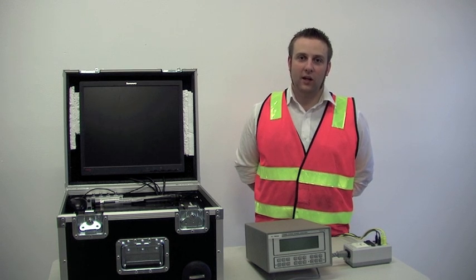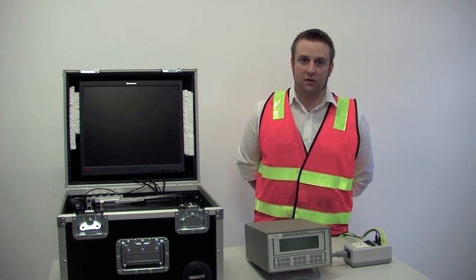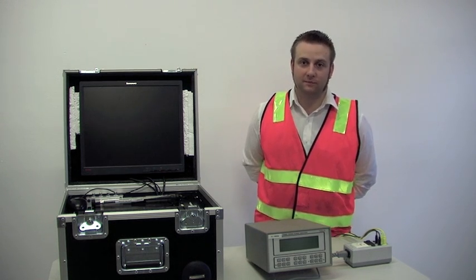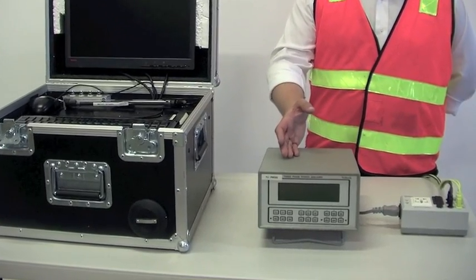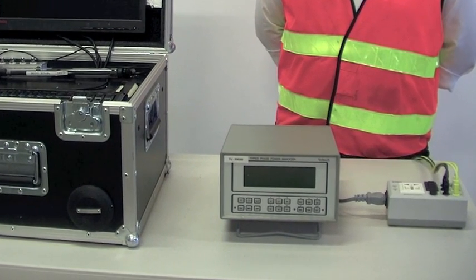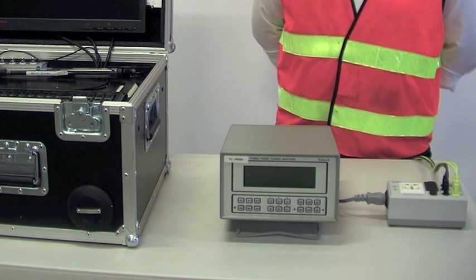Along with the test rig we have two other measurement devices. We have our power analyzer and our sound measurement device. Using our power analyzer we can measure input power, voltage, current, total harmonic distortion as well as power factor.